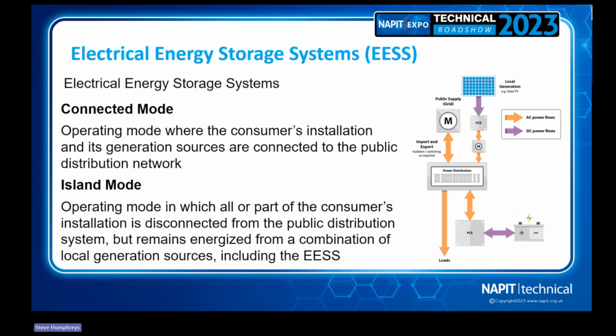A bit of basics on the electrical energy storage systems themselves. You can either have it in connected mode, and from that diagram from the code of practice, we've got local generation from solar PV coming into an inverter. Where you see the term PCE, that's what the code of practice calls it - to me and you, we're talking about the inverter really, although in these circumstances the inverter is much more than an inverter, it's doing lots more. It's the brains of the operation really - power conversion equipment is its proper terminology.